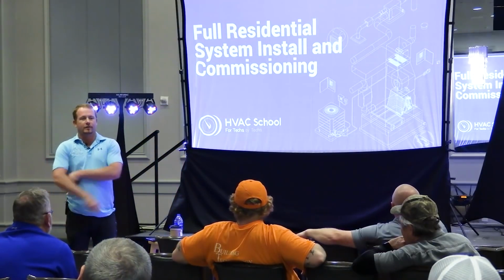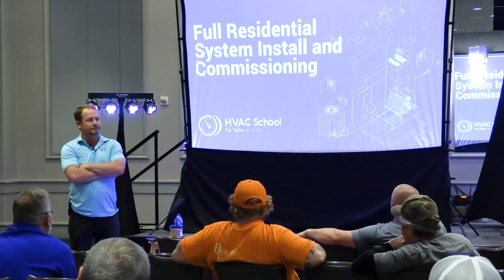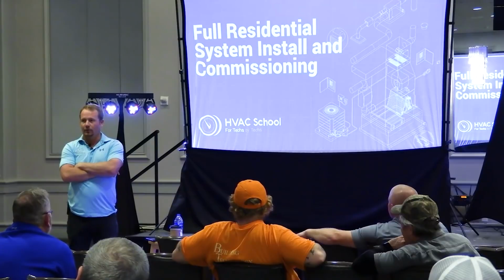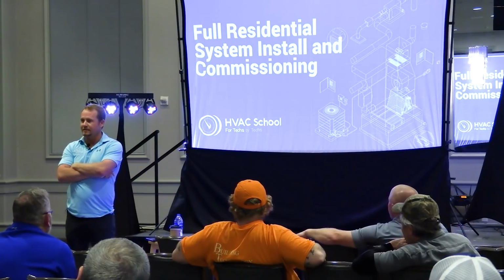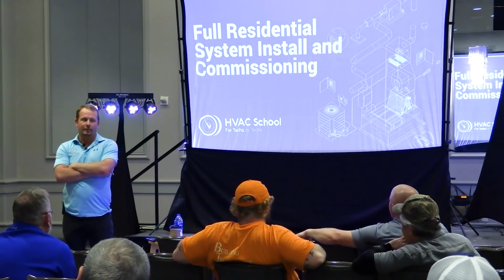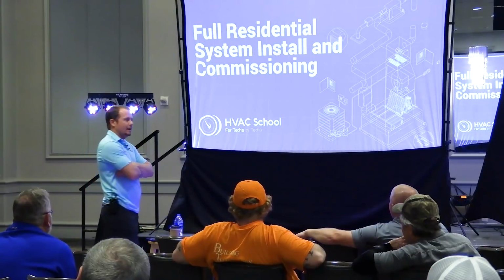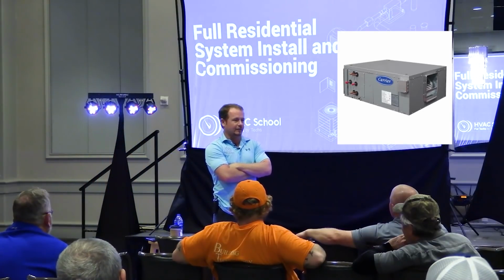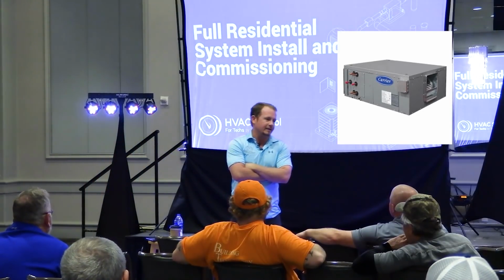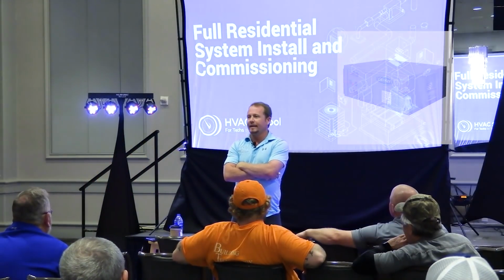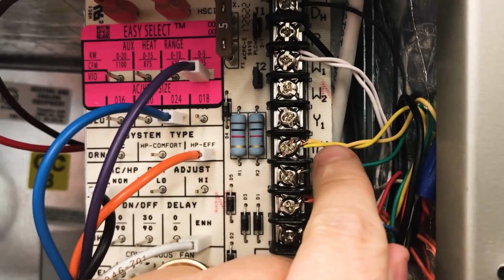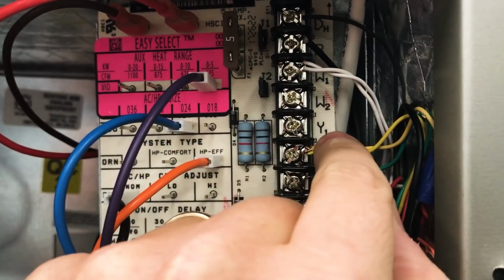What is the static pressure of the system when it is off? Lower. So that means we have great airflow when the system's off, right? Hopefully you're getting where I'm going with this. What happens if you set up your airflow, you have a variable speed air handler, let's say it's a Carrier, it doesn't really matter what it is, and somebody lands the yellow wire on the Y1 terminal rather than the Y/Y2 terminal.